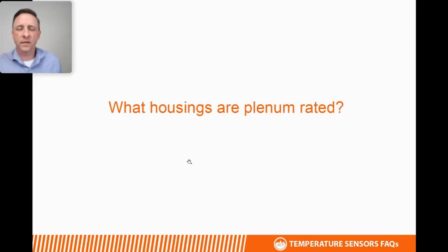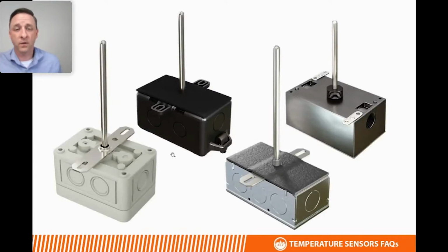Which of the standard duct housings are plenum rated? If you look at the screen, the three housings on the right-hand side of the screen, the black plastic box, the metal galvanized box, as well as the NEMA 3R aluminum bell box, are all plenum rated. The only one that is not is the polycarbonate NEMA 4X housing.